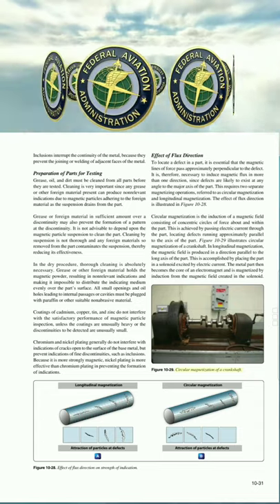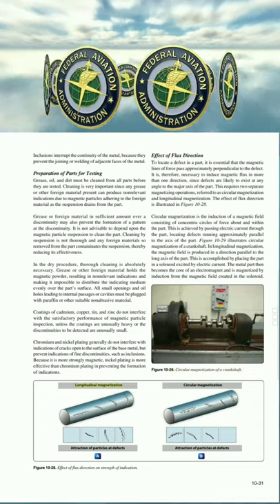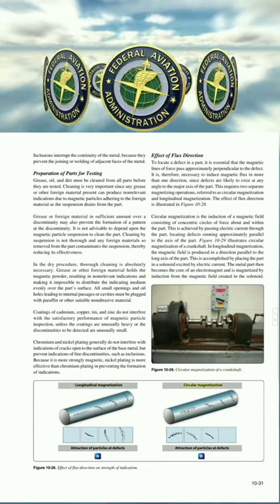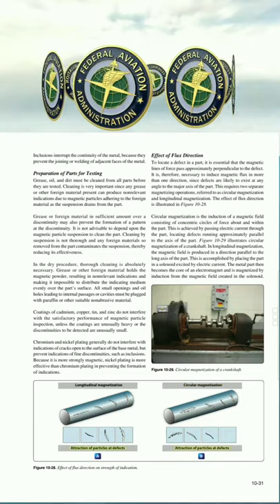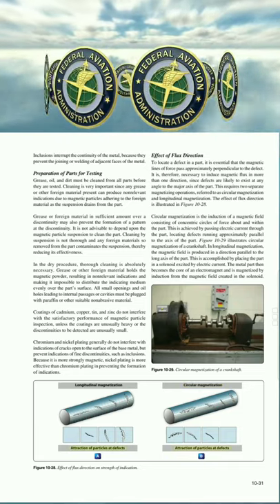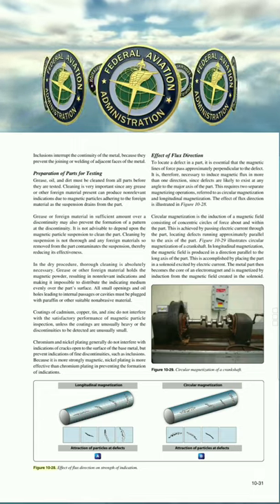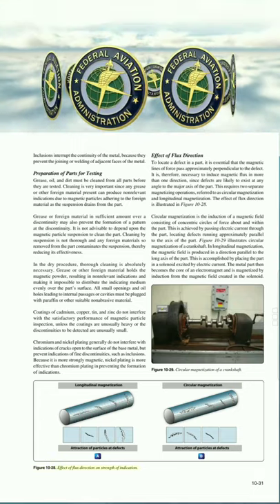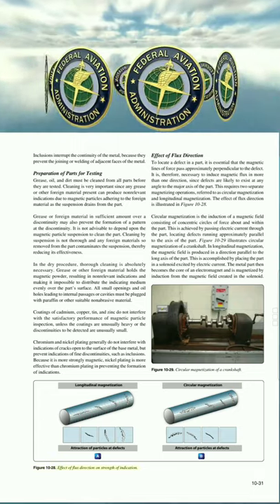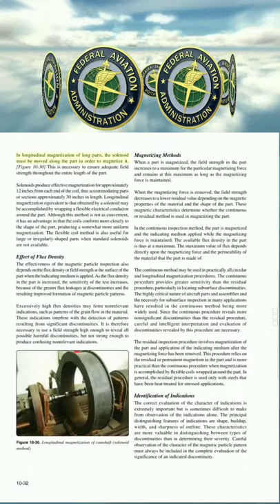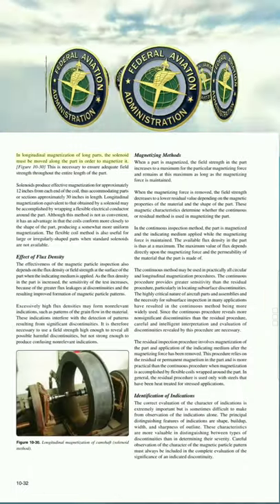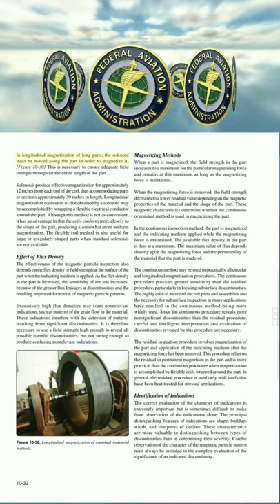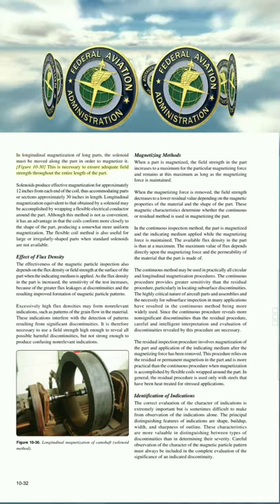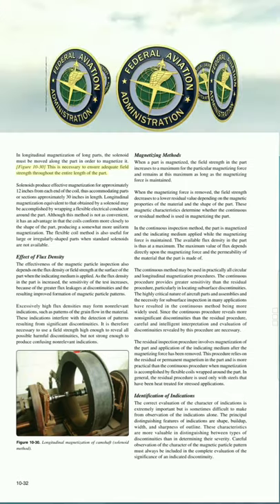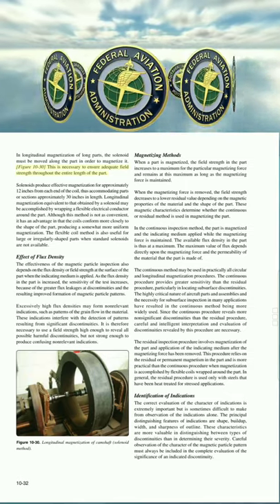Figure 10-29. Circular magnetization of a crankshaft. Longitudinal magnetization. Circular magnetization. Attraction of particles at defects. Figure 10-28. Effect of flux direction on strength of indication. In longitudinal magnetization of long parts, the solenoid must be moved along the part in order to magnetize it. Figure 10-30. This is necessary to ensure adequate field strength throughout the entire length of the part.